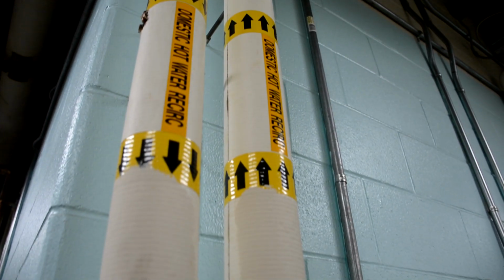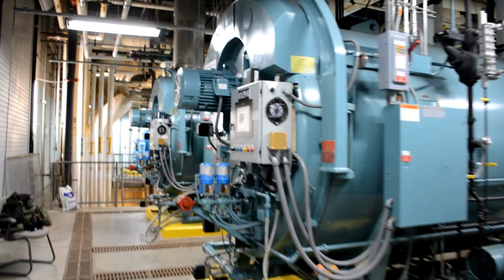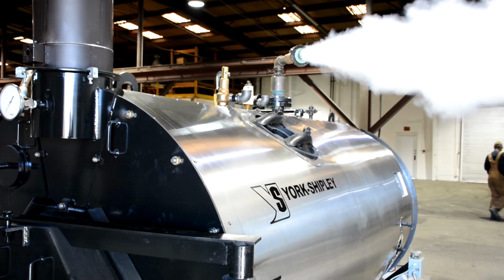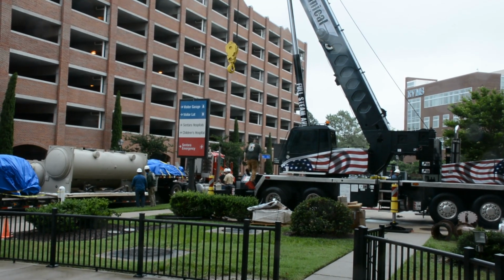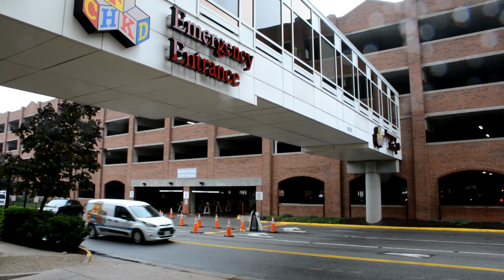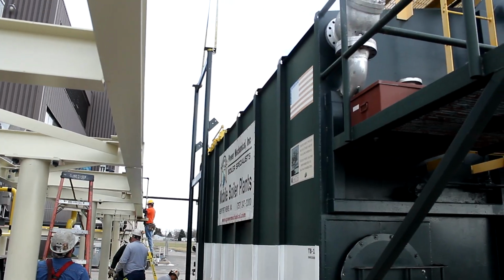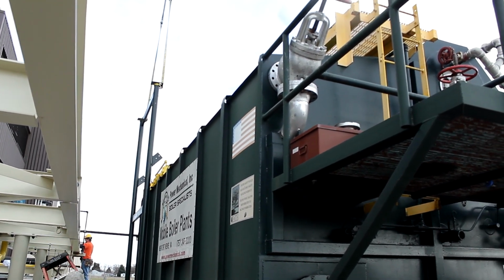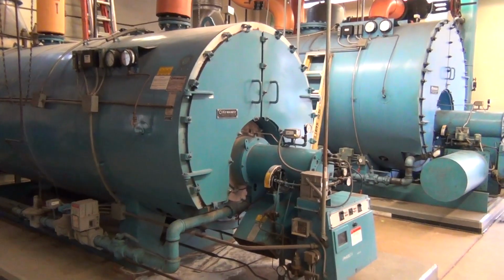That said, some systems will still have boilers installed for steam and others for hot water, and could even have a separate system for their domestic hot water needs. The point being that there's just no one size fits all to the multitudes of plants and demands out there, so each one will be designed independently. Steam, however, does offer the maximum versatility for a system without having additional units. Systems that need numerous different applications, like a hospital, hotel, or manufacturing facility, may use one large capacity steam boiler with various accessories and ancillary equipment to provide these hot water needs. The point being that the steam can be utilized to make hot water, but the opposite is not possible without another source adding extra energy to the water. For a system that may only need hydronic heat or hot water, a boiler can be trimmed to meet those demands alone.